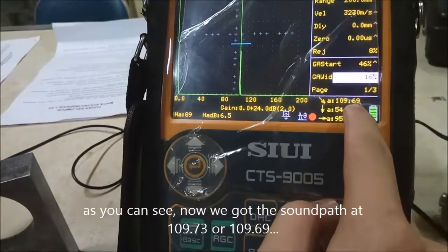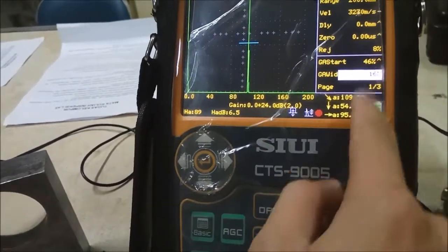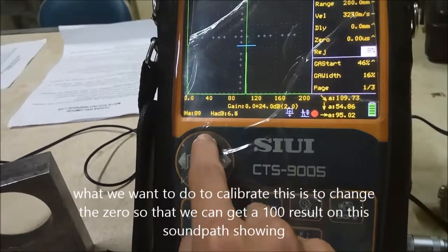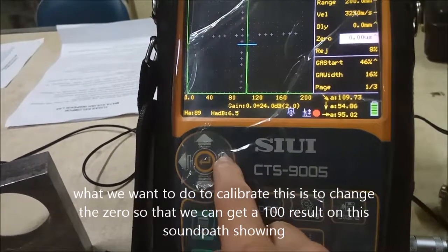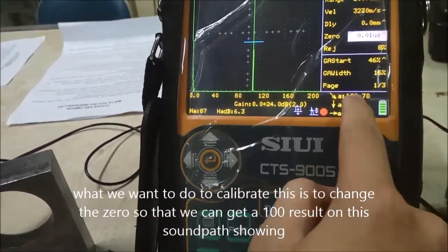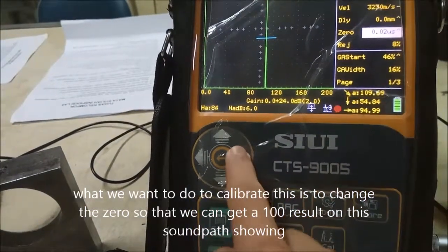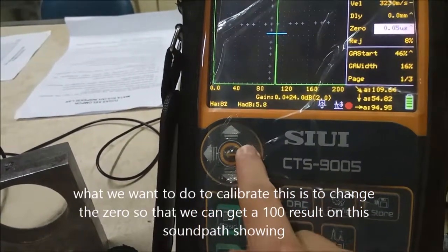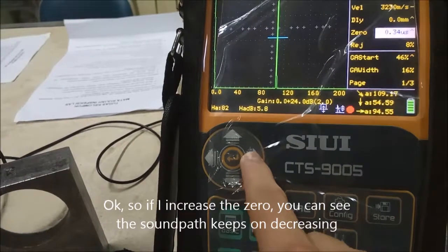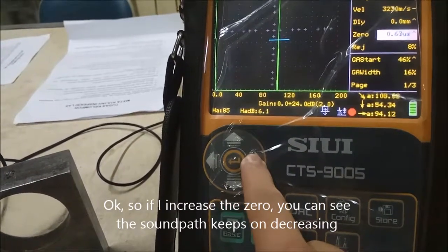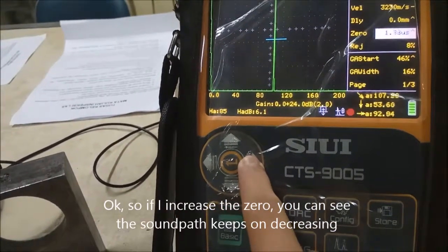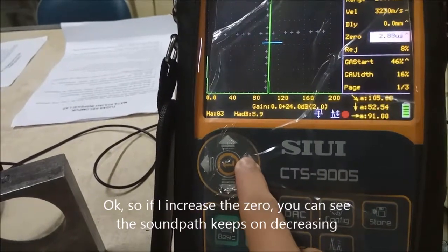109.73 or 109.69. What we want to do to calibrate this is to change the zero so that we can get 100 result on this sound path showings. Okay, so if I increase the zero, you can see the sound path keeps on decreasing.